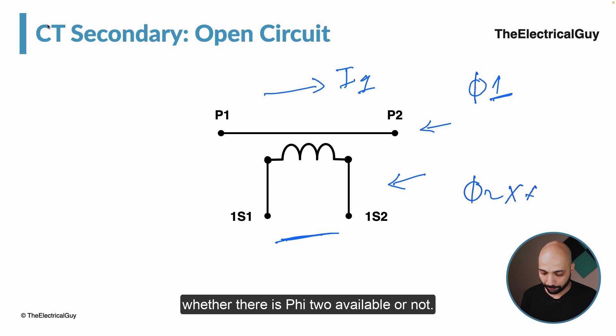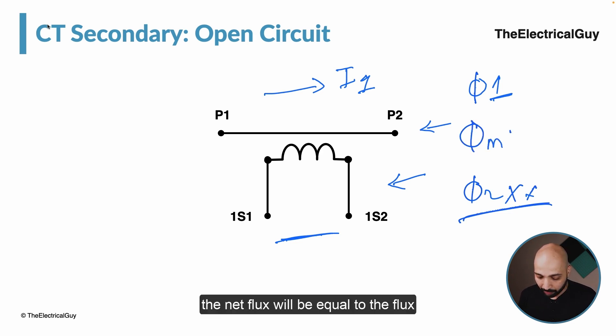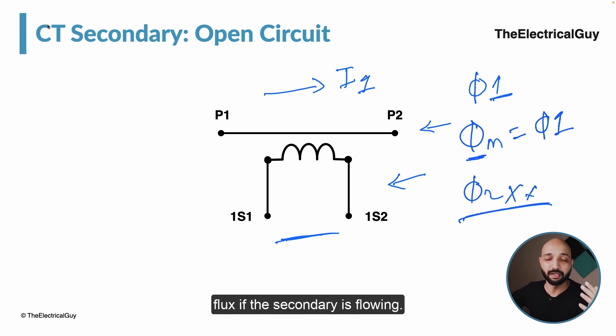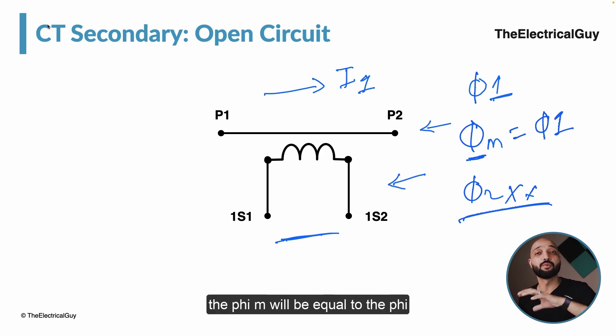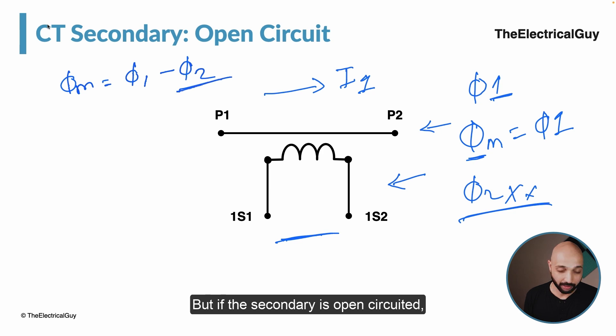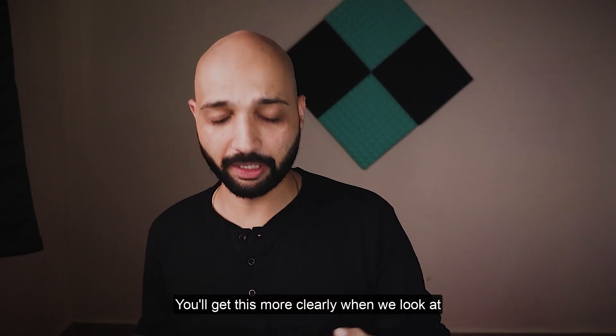There will always be phi_1 available whether there is phi_2 or not. If the secondary is open circuited, the net flux phi_m equals phi_1, because there is no opposing phi_2. Normally phi_m equals phi_1 minus phi_2, but with open secondary there is no phi_2. So phi_m equals phi_1, which can be very high, causing core saturation and a very high secondary voltage.